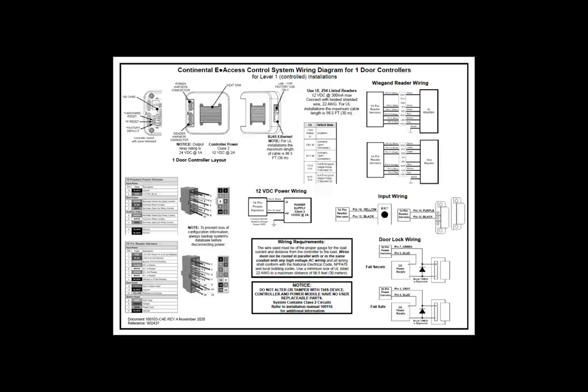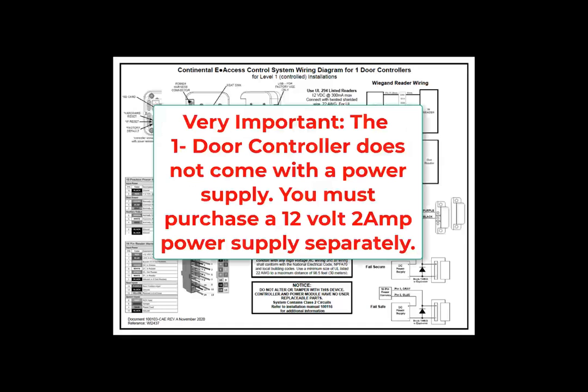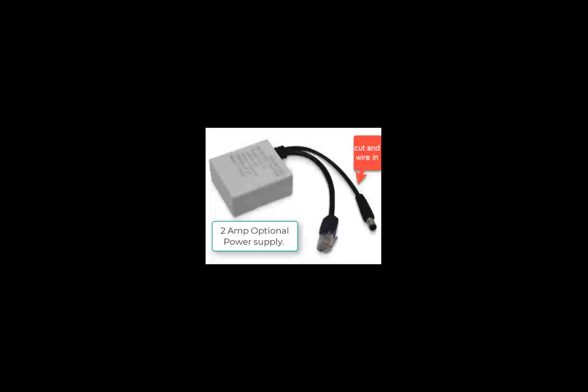The 1-door controller contains 2 connectors, a 14-pin reader harness and a 10-pin power harness. Please take note of the power requirements that can be found in the installation guide. Continental offers an optional PoE power supply that can provide up to 2 amps and can be wired into the plus 12 volt and ground inputs. Very important! This option is not for PoE and does not plug in to the Ethernet jack. Again, it is only used as an external power supply.